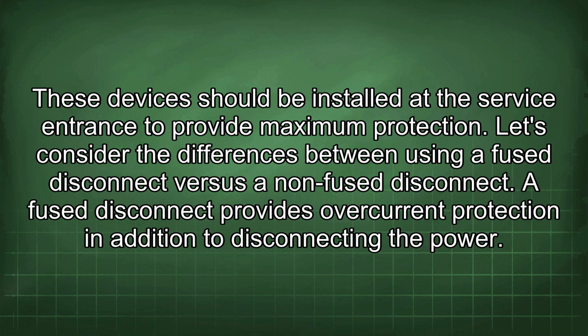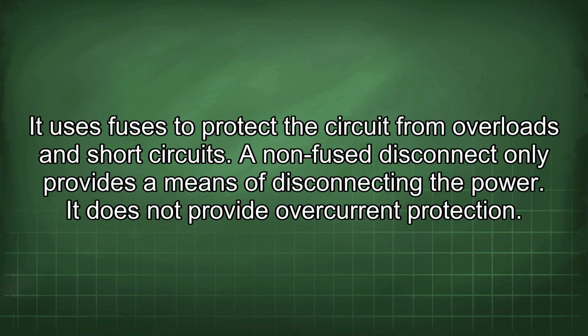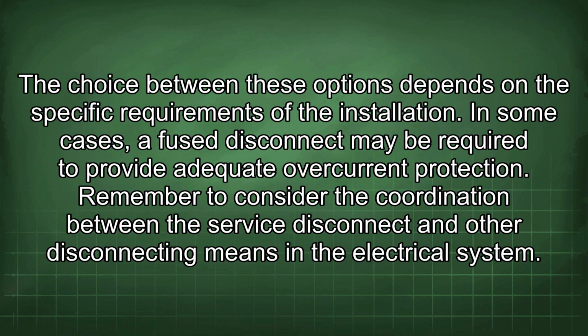Let's consider the differences between using a fused disconnect versus a non-fused disconnect. A fused disconnect provides overcurrent protection in addition to disconnecting the power. It uses fuses to protect the circuit from overloads and short circuits. A non-fused disconnect only provides a means of disconnecting the power. It does not provide overcurrent protection. The choice between these options depends on the specific requirements of the installation. In some cases, a fused disconnect may be required to provide adequate overcurrent protection.